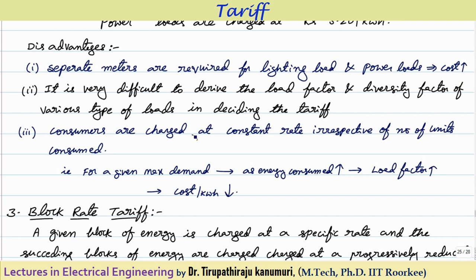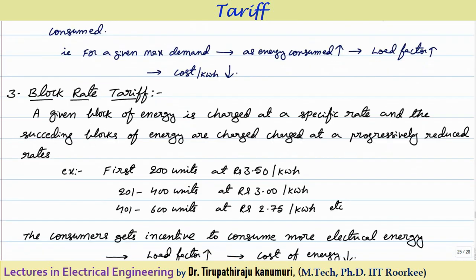Another limitation is that consumers are charged at a constant rate irrespective of the number of units consumed. That means for a power load, we are telling it is only 3.20 per kilowatt-hour whether he uses one hour or 10 hours — we are charging at the same rate. Then why would the consumer use it continuously for more time? Some incentive should be given to encourage operating for more time. That is not provided in this tariff. For a given maximum demand, as the energy consumed increases, automatically load factor increases, so cost per kilowatt-hour decreases.